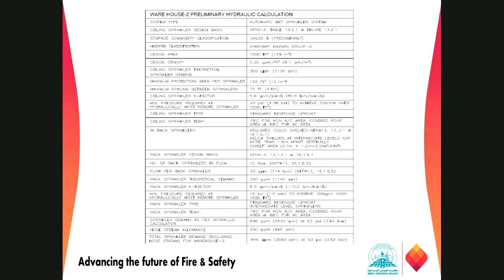Then we have the hydraulic calculation information sheet, right? The preliminary hydraulic calculation report, right? We call it hydraulic calculation sheet. This information should always be pasted. It should always be on the drawing, normally on the general plan or general layout drawing of the sprinkler system. There should be some table which gives us the complete information regarding the plan of those buildings.